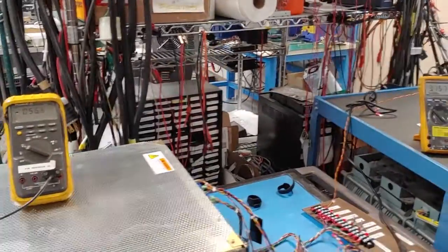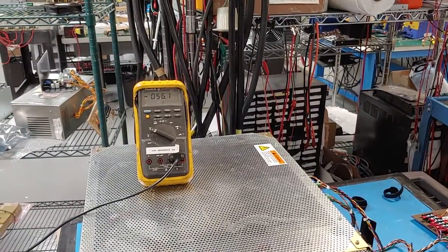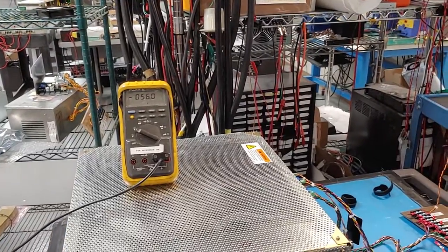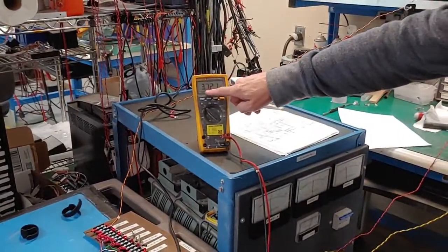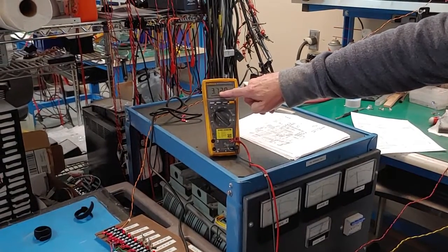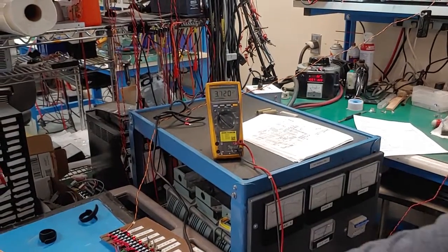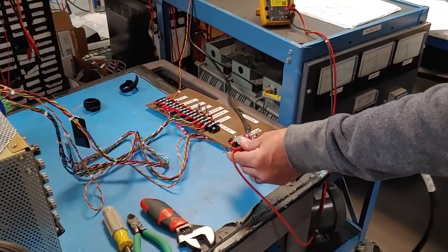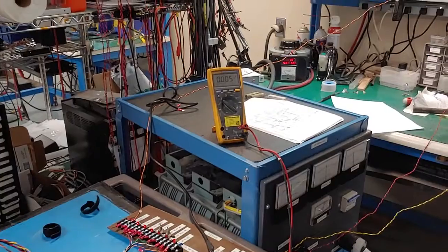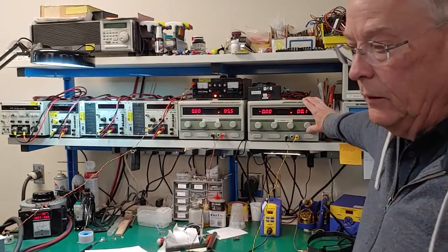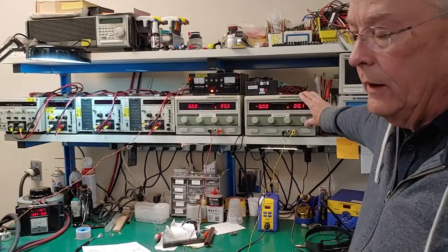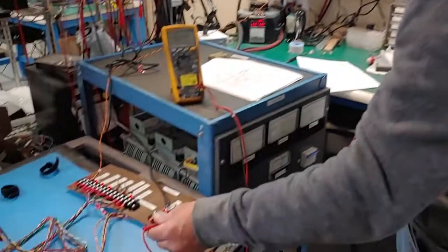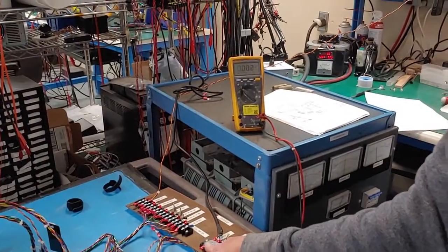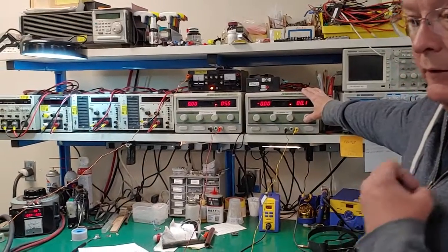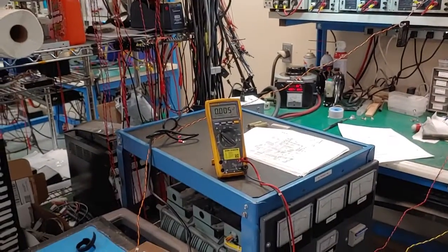You let that settle for a second. Okay, so it's going to settle at about 56,000 volts, and my current reading right now is 37.2 milliamps. I'm going to move over to monitor my filaments, which should be 0 at this time, and then I'm going to command the drive circuit so that it tries to make the current I'm looking for, which was, what did I say, it was 3.7? 3.7. Okay, so roughly at about 3.7 volts here, which means I'm going to command it to give me the current necessary to run at 37 milliamps.